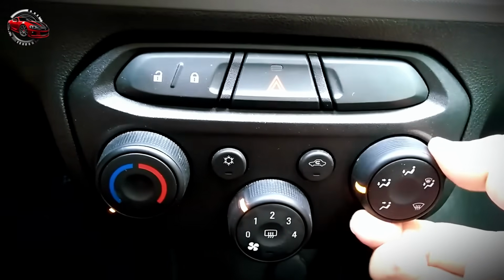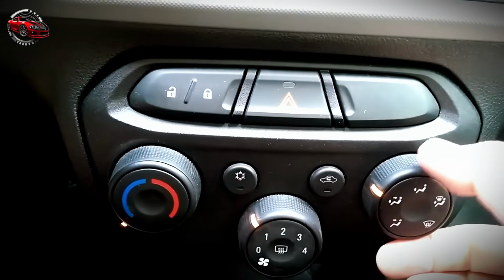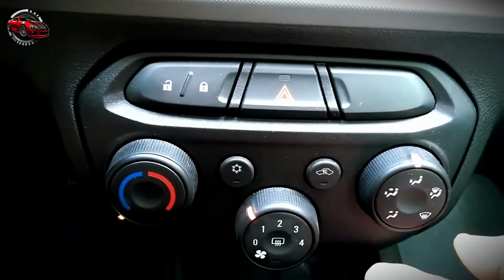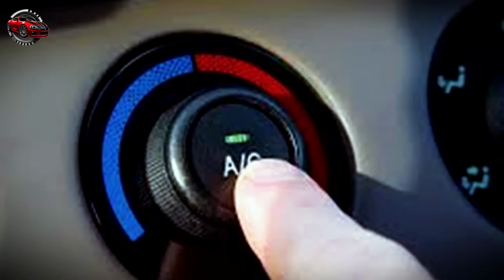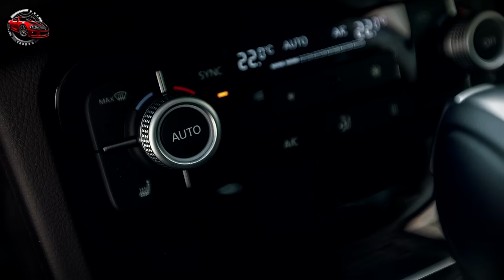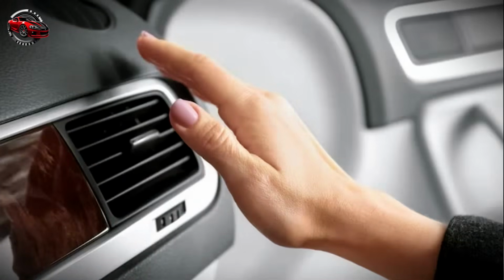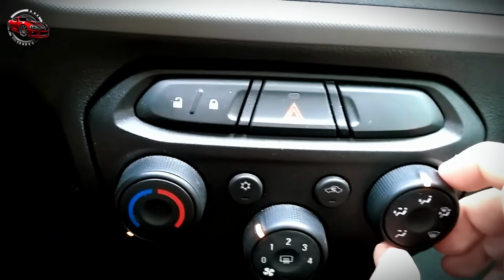Job 1 is to cool the air, which we call removing sensible heat. Job 2, and this is the one that takes all the energy, is to pull the moisture out of that air. We call that removing latent heat. It has to literally condense that humidity into water, which is why you see water dripping under your car. That process saps a massive amount of cooling power.